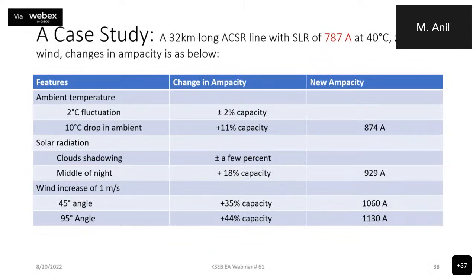And a case study is presented with a 32-kilometer long ACSR line with a static line rating of 787 ampere at 40 degrees Celsius, zero wind. Changes in ampacity are as below. That is, the static line rating, which is the thermal overload limit of the conductor being used, is 787 ampere at 40 degrees Celsius. So, based upon the ambient temperature condition, how the loading or ampacity can be changed. So features: for ambient temperature, a 2 degrees Celsius fluctuation means a change in ampacity of only plus or minus 2% of the capacity. A 10 degrees Celsius drop in ambient temperature can entail additional capacity utilization of 11%, which results in the new ampacity going from the 787 static line rating to 874 amperes.